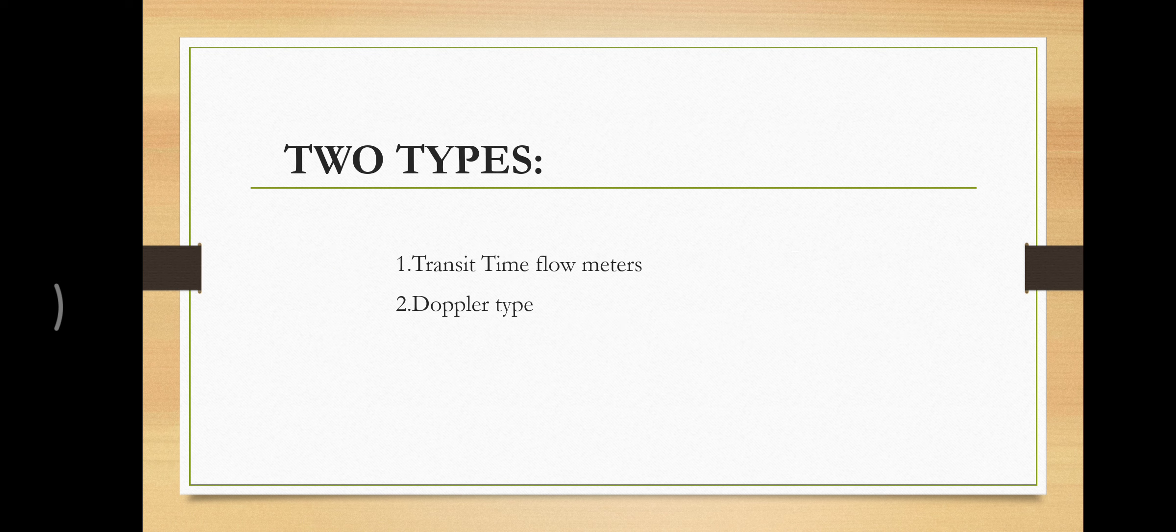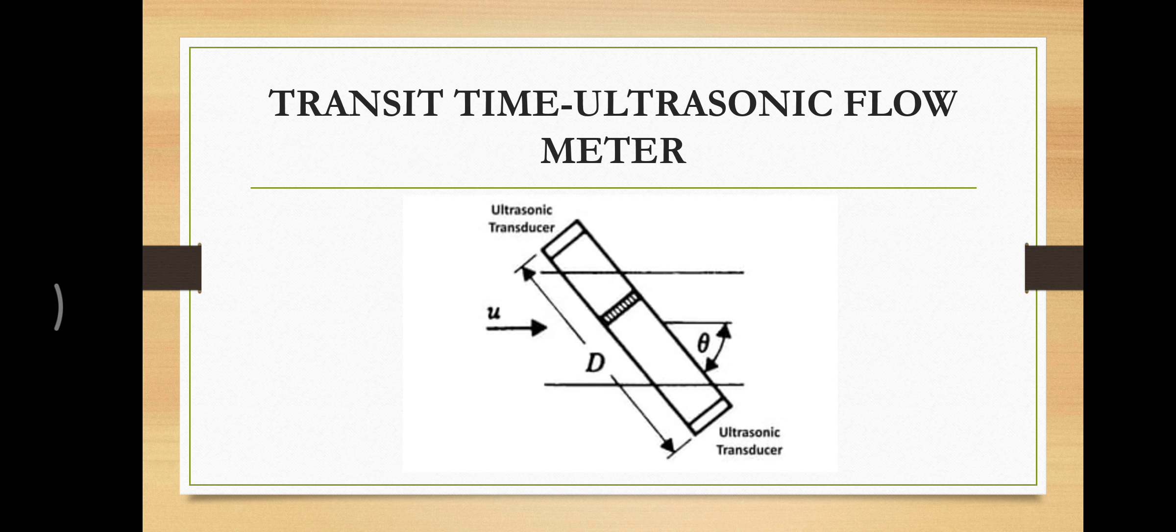It has two types: transit time flow meters and Doppler type. First of all, transit time ultrasonic meter. In a transit type, it consists of two ultrasonic transducers. The distance between the two ultrasonic transducers is capital D. The blood flowing in a direction is U, and the two transducers are placed at an angle theta.